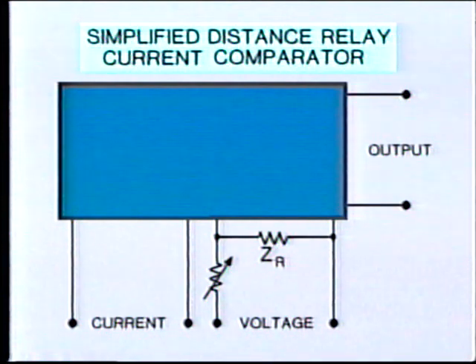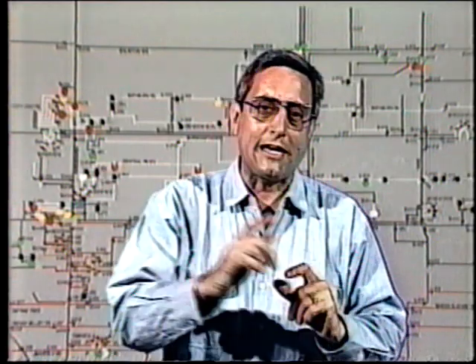In this case, the VT voltage signal is applied across the replica impedance so as to produce proportional current. In a simple impedance relay, the direct amplitude comparator may be satisfactory, allowing tripping on high current and low voltage. However, for the more sensitive distance relays, it is essential that the phase angle and direction of fault current be accounted for. Hence, some form of phase comparison must be used.